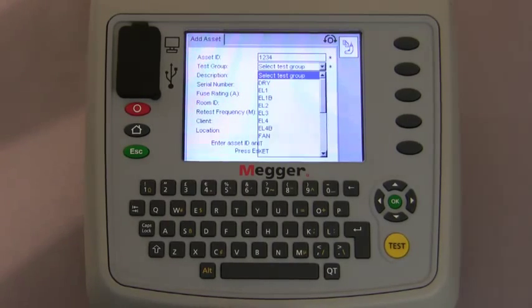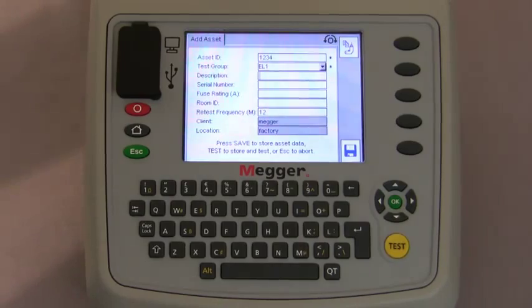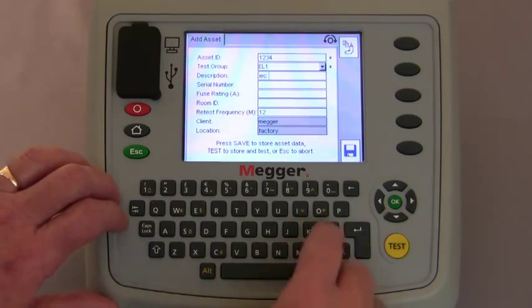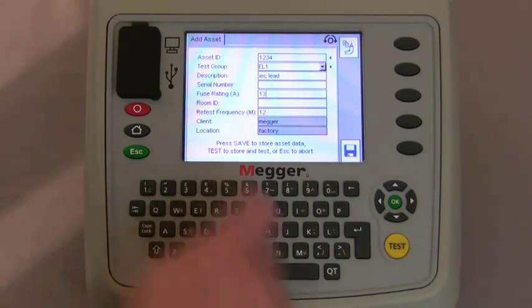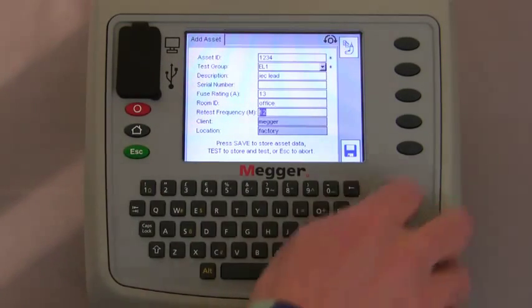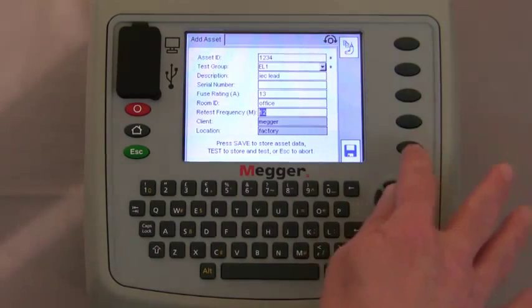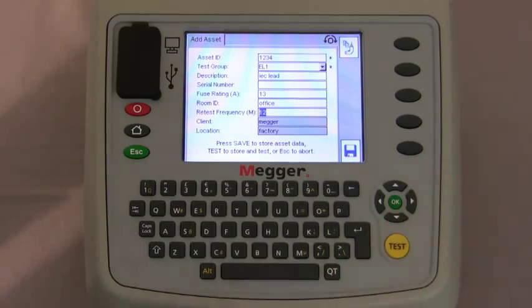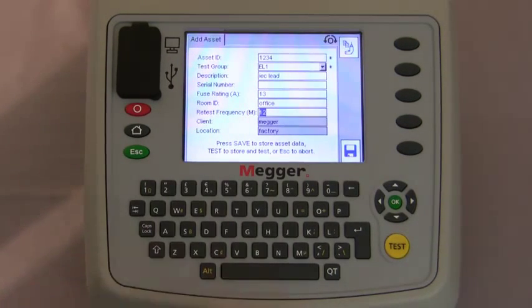In this instance we're going to test a class 1 extension lead, so we scroll down to EL1 and press the select key. Using the navigation keys we move down and type in the description, serial number if applicable, the fuse rating, and the room the equipment is in. Moving down we have the retest frequency and the client and location of Megger and the factory. At this point you can press the hot key to save the asset to memory, or press the test button to save it and commence testing. If you have duplicate pieces of equipment, you can press the hot key to bring the information up for the next asset and simply change the asset identification and any descriptions.